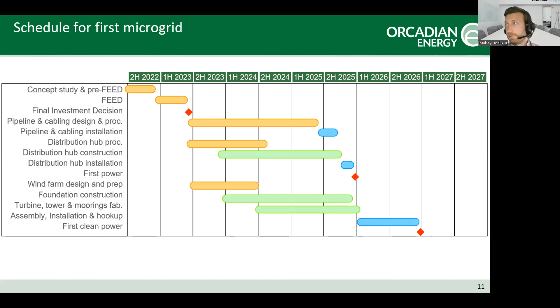So what are the advantages of the Orcadian Microgrid? Firstly, we're transforming intermittent renewable energy into reliable low emissions energy for offshore facilities. We're minimizing brownfield modifications for those assets by dropping the voltage down to 33 kilovolts, so the power transmitted to these platforms is only at 33 kV. We can drop that lower, but that's a conversation with each consumer, since you'd have to increase your core size and there's a cost associated with that.